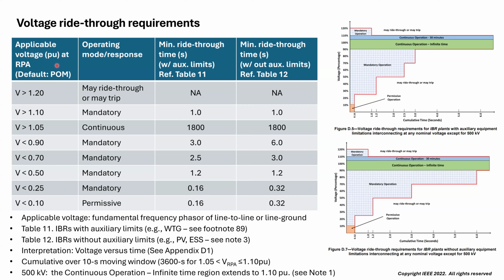If we look at the left side of this chart, it talks about the applicable voltage at the reference point of applicability. By default, that reference point of applicability is going to be the point of measurement. And the applicable voltage is the fundamental frequency phasor component of either the line-to-line or the line-to-ground voltage. So, as a result, one could think of an example, say, where a three-phase fault, a line-to-line fault, and a line-to-ground fault may all have the same ride-through duration requirements. So that's the implication of it either being line-to-line or line-to-ground voltage.